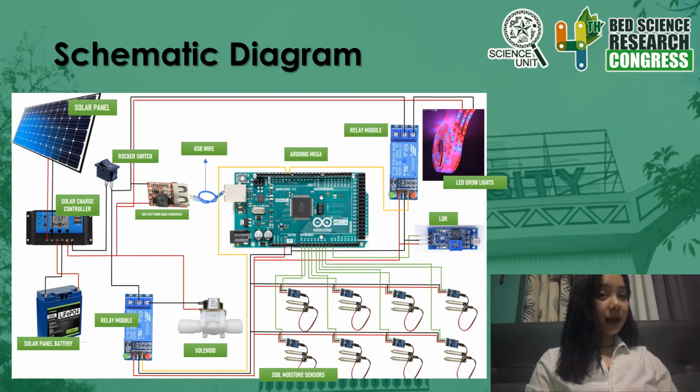For the schematic diagram, the connection starts in the solar panel. The solar panel is connected to the solar charger controller, which is also connected to the battery. The solar charger is important so that the flow of electricity goes directly to the battery. The output of the solar charger is connected to the rocker switch.